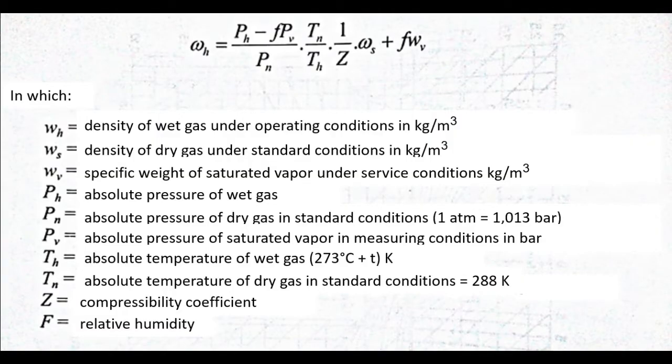The addition of steam to a certain amount of dry gas influences the flow rate corresponding to a given differential pressure in two ways. One, the density of wet gas changes relative to that of dry gas. Two, the measured gas is only a part of the mixture that passes through the element.